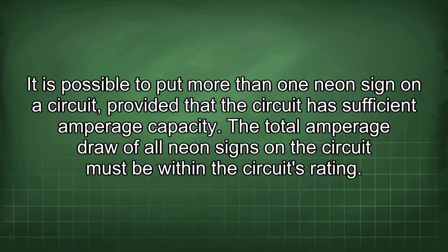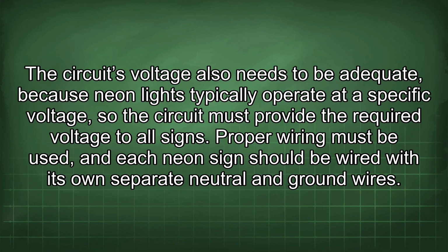It is possible to put more than one neon sign on a circuit, provided that the circuit has sufficient amperage capacity. The total amperage draw of all neon signs on the circuit must be within the circuit's rating. The circuit's voltage also needs to be adequate, because neon lights typically operate at a specific voltage, so the circuit must provide the required voltage to all signs. Proper wiring must be used, and each neon sign should be wired with its own separate neutral and ground wires.